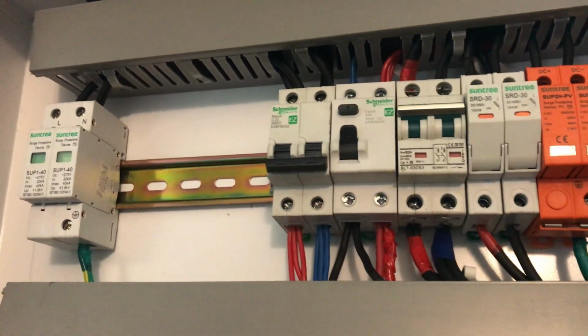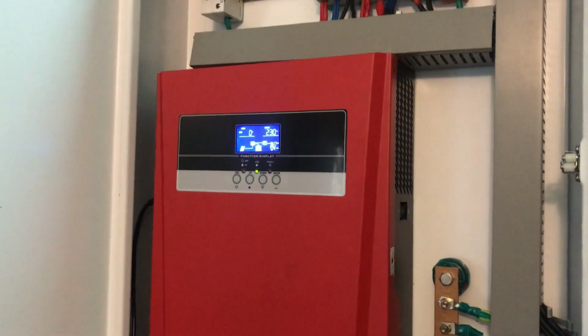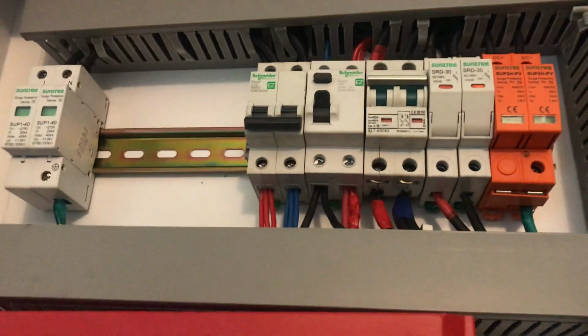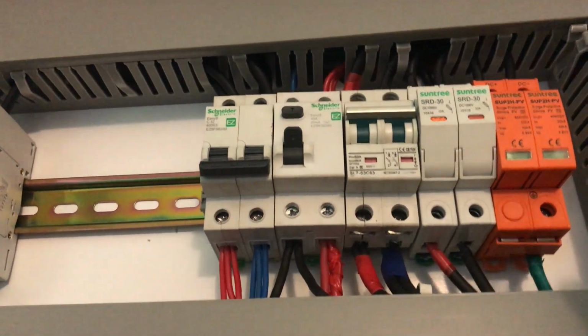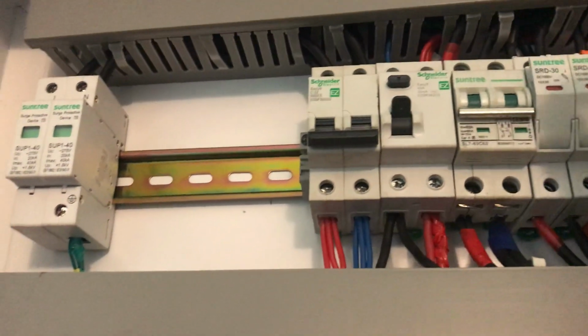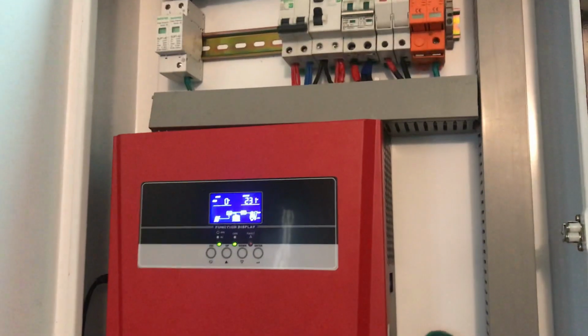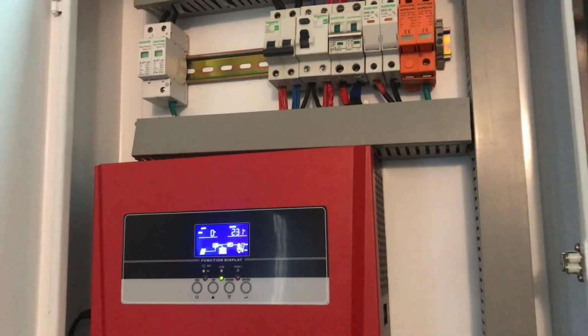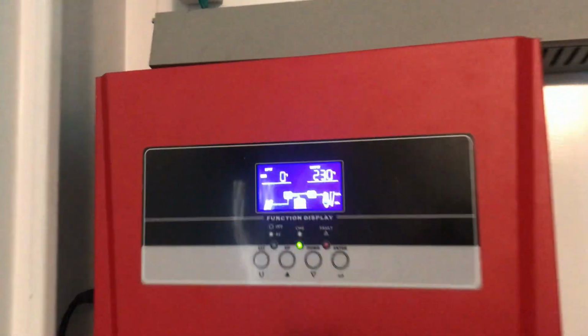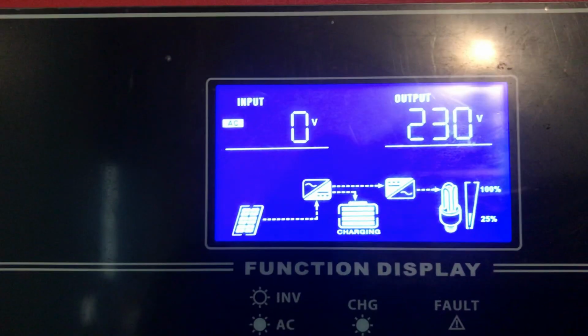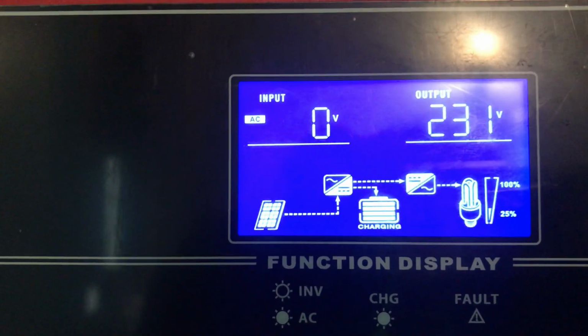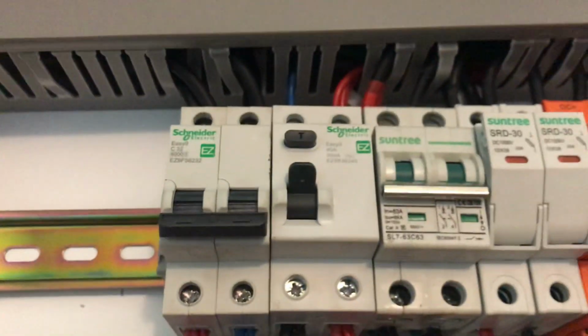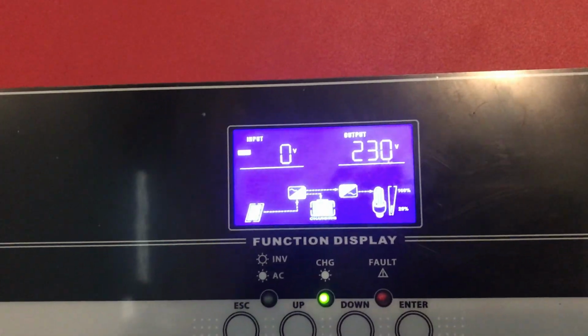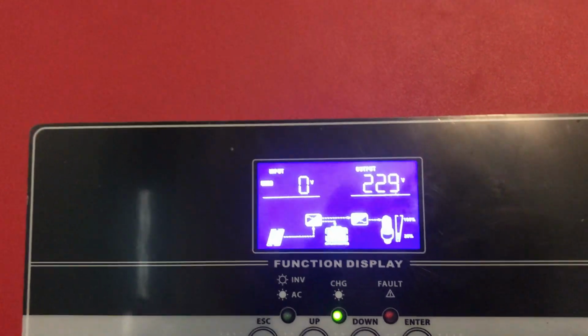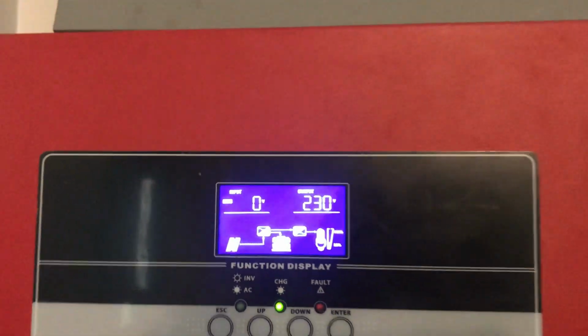So this is the inverter. And the good part of this inverter is it can also run without the batteries. So I can turn the battery off and it's purely running on solar panels. So solar panels directly to the inverter, and the system is holding on pretty well. So there are no batteries. But this one's showing the battery is connected, but it's definitely not connected, and the power is coming through the solar panels directly into my load.